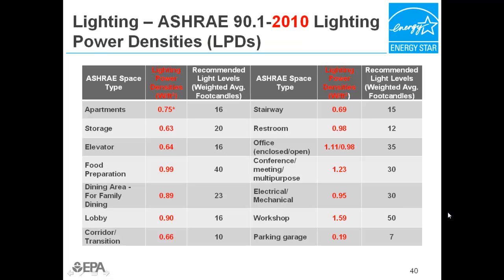As you can see in this table, the lighting power densities, or LPDs, from ASHRAE 90.1-2010 have been listed for common spaces frequently found in multifamily high-rise buildings. This table is located in the Notes section of the Prescriptive Path document. Apartment dwelling units are not listed as a space type in ASHRAE, so lighting power density for highway lodging guest rooms was used instead.